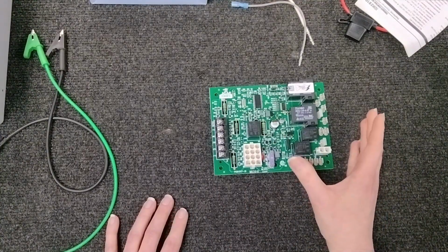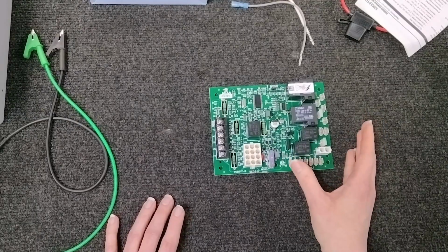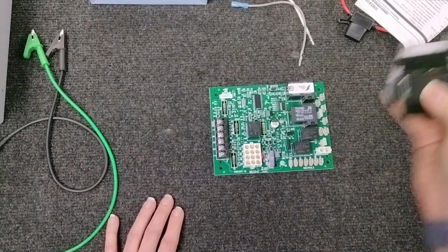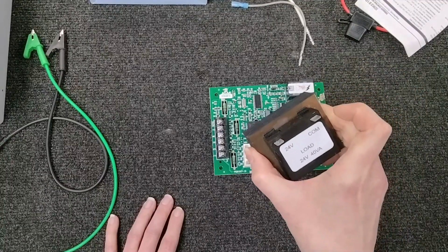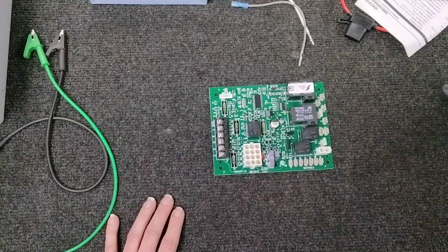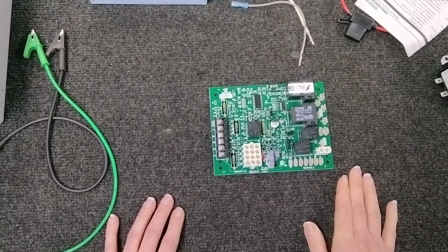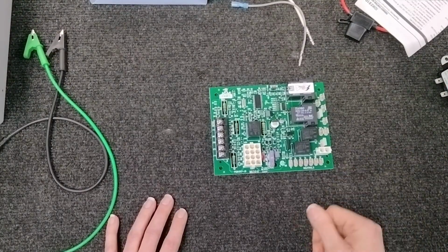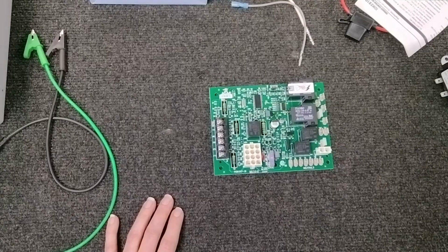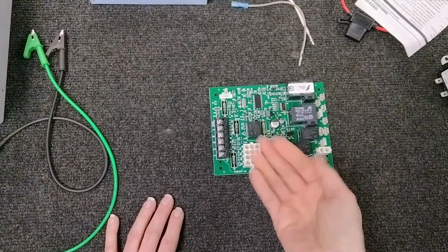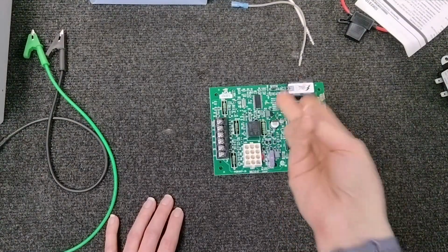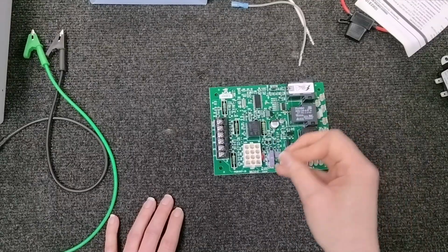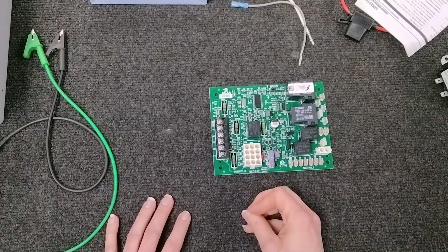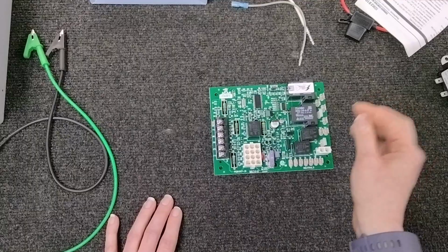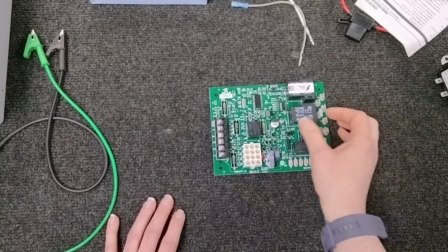So always, first and foremost, make sure you do have power and make sure that your transformer is sending that 24 volts and that your door switch is actually functioning like it should. Because if you know you're getting power to the unit, but there's no power getting into the unit, it's going to be the door switch on your gas furnaces more than likely.